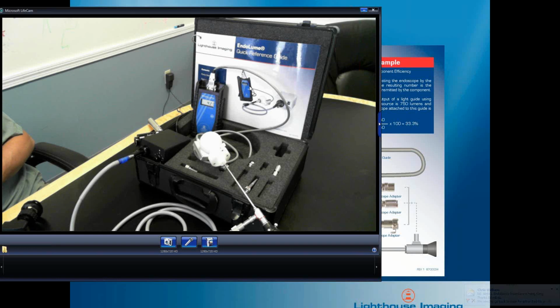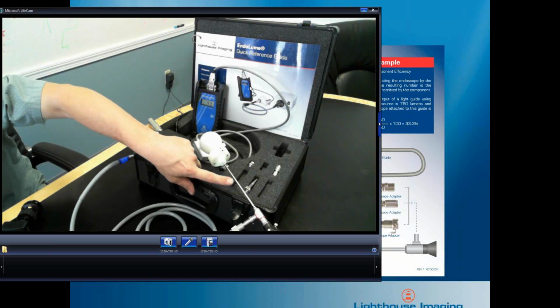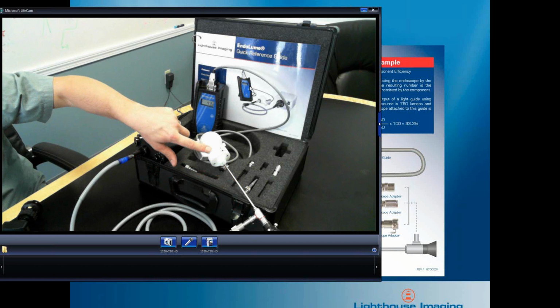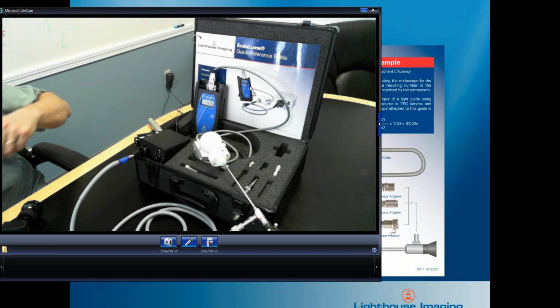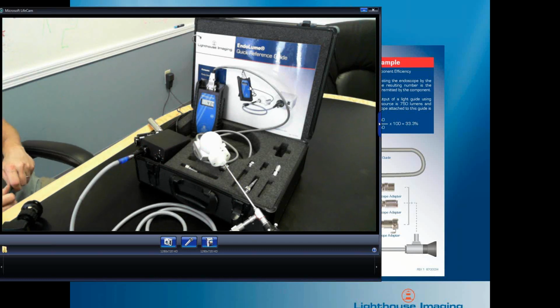So if we recall from our sheet before, we said that for a 4mm arthroscope, it should be around 10 to 12.5% minimum. So we're right on the edge. This scope maybe has a little bit of loss in the collector on the side, or maybe in some of the fibers, or maybe there's some scuffing on the tip. So it's a little bit low for this type of scope, but it's on the edge of acceptable. I would probably pass it at this point.